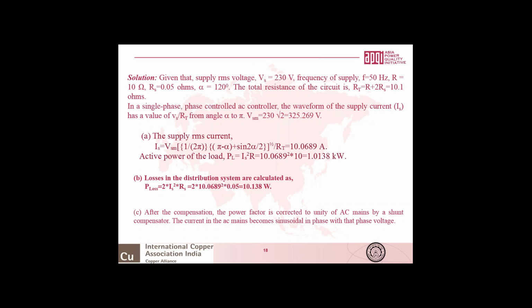And active power of the load now becomes IS square R, that is only in the load. So current square into 10, that becomes 1.0138 kilowatt. So that's the active power consumed by the load. And the losses in the distribution system are calculated as 2 into IS square into RS. So 2 into the current which is already calculated above, 10.0689 square, into 0.05, and that becomes 10.138 watt. Now after the compensation, the power factor is corrected to unity of AC mains by shunt compensator, which is used before the AC controller across the point of common coupling.